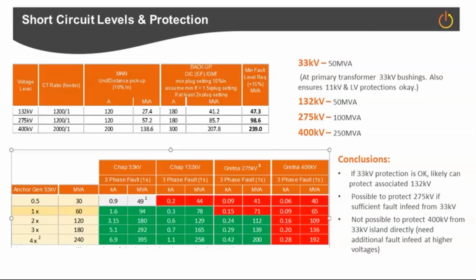Short circuit levels and protection. So this is interesting as well. I talked about the charging power of a generator, but also there's the impact of short circuit levels on system protection. Certainly at the transmission voltage levels, 275 and 400 kV, the protections are very fast acting, in the range of about 50 milliseconds for a zone 1 distance scheme. So very fast acting. Less so at 132 and 33 kV.